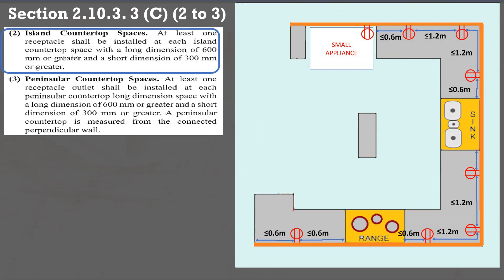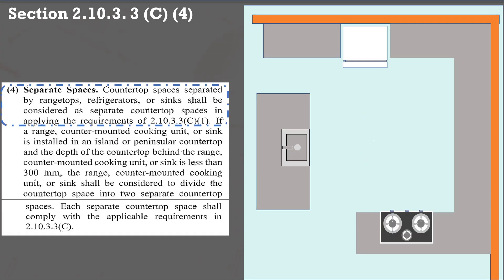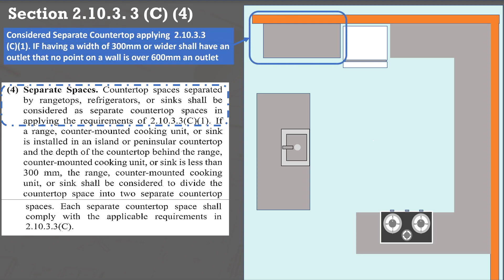Island countertops with dimensions of 600 mm or greater on the long side and 300 mm or more on the short side shall have at least one outlet. For peninsular countertops, at least one receptacle outlet is required if the long side is 600 mm or more and the short side is 300 mm or more. If a counter is separated by an appliance such as a refrigerator, range top, or sink, it is considered a separate countertop space and shall comply with paragraph C1 — countertops 300 mm or more in width shall have a receptacle outlet that no point on a wall is over 600 mm.